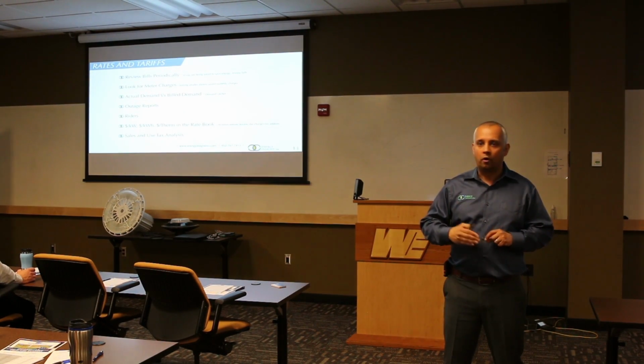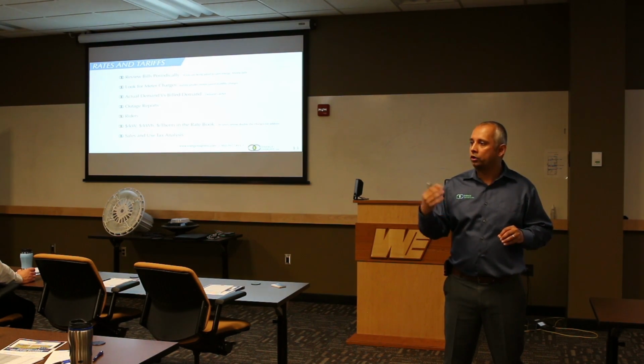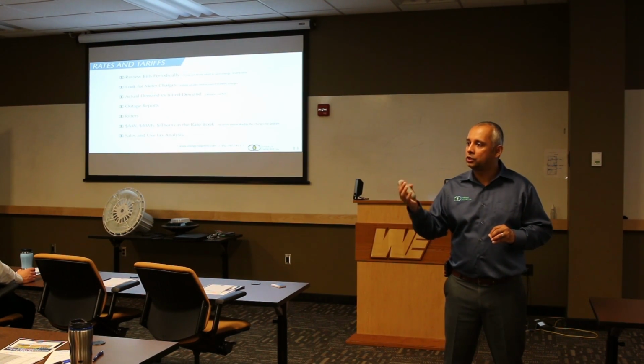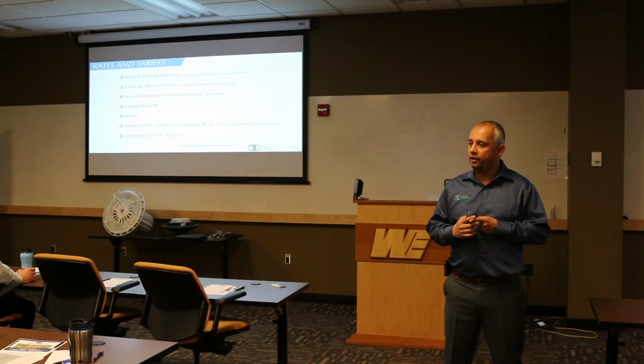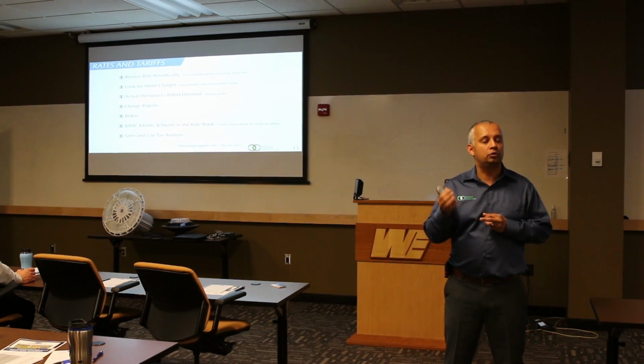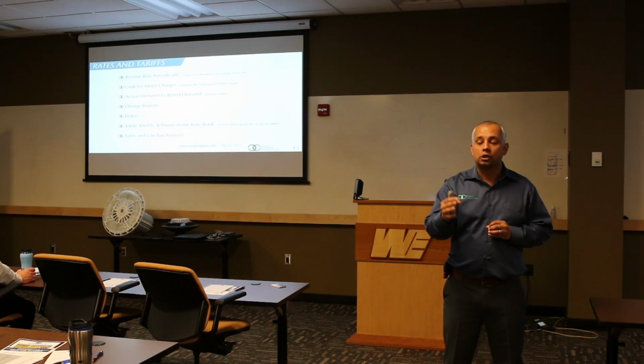So we asked the question: how come all of a sudden you're using 150 kW or 500 kW more than your average? After some digging, talking to plant managers and people on the floor, we learned they'd had a huge outage - somebody took the line out or something happened. So we went back to the utility and told them the reason. First thing they did was take them off the ratchet. Second, they gave them a reporting process: every time you have an outage, track it on paper and fax it to us so we know it's happening because of us. So they got a huge refund back, because they weren't supposed to be charged for that, but it happened to them.